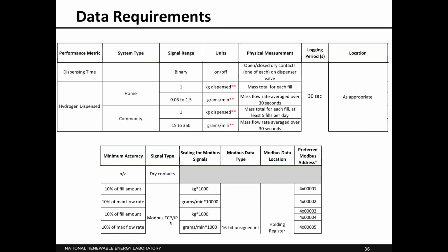Further down the list, we see dispensing time, and we're going to measure that with a binary on-off, which is just a set of dry contacts that will be on the main on-off valve of your dispenser. So that's just going to be a binary value that will be reported, again, to us directly. That's an isolated signal. And then we'll have hydrogen dispensed. You can't see the footnotes here, the double asterisks, but on the requirements document, you're required to measure one, but not both of these, because we can calculate one from the other. So you need to give us at least one of these.